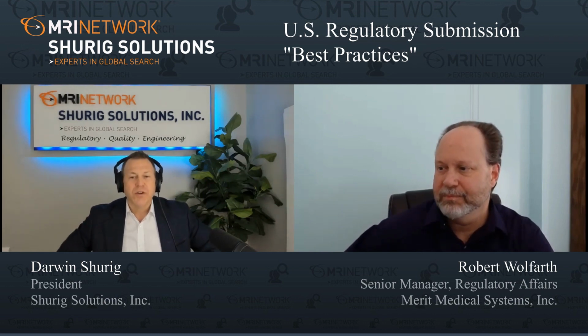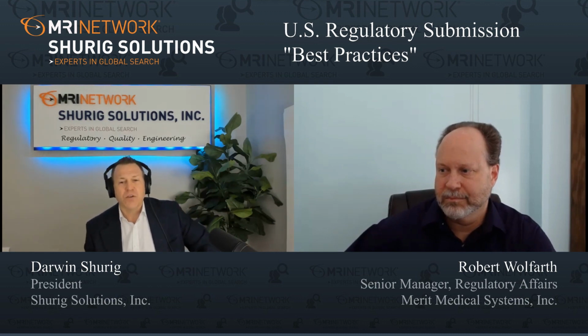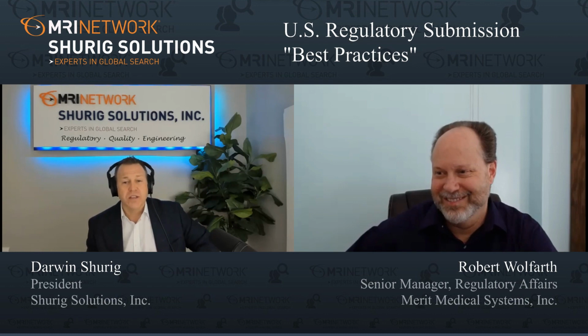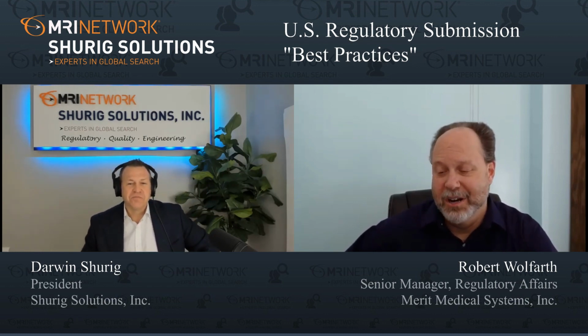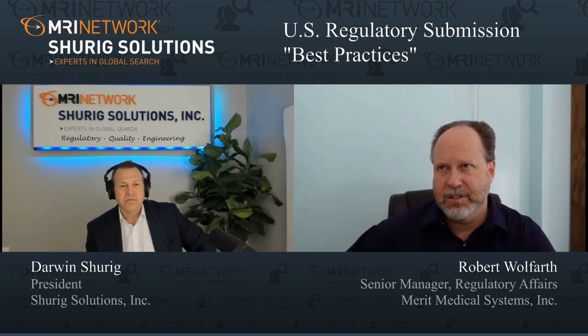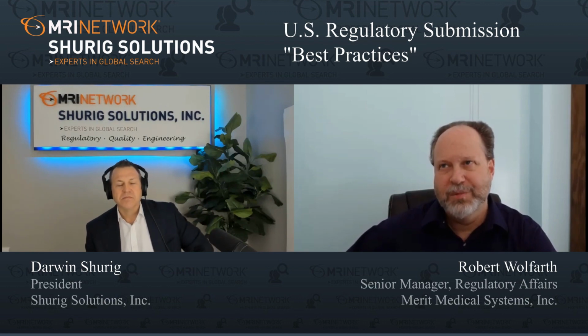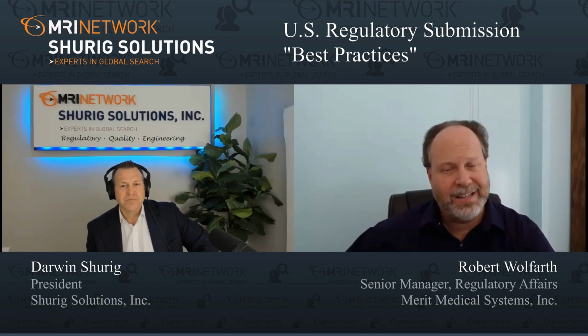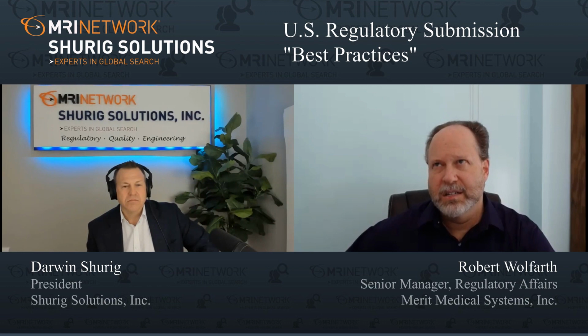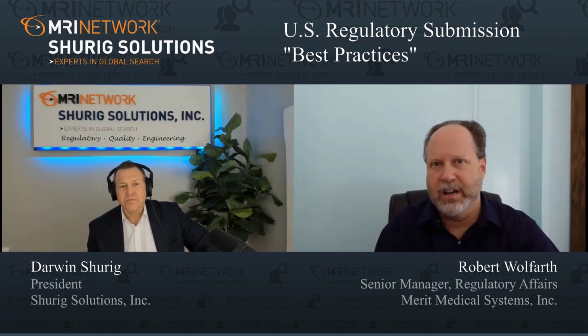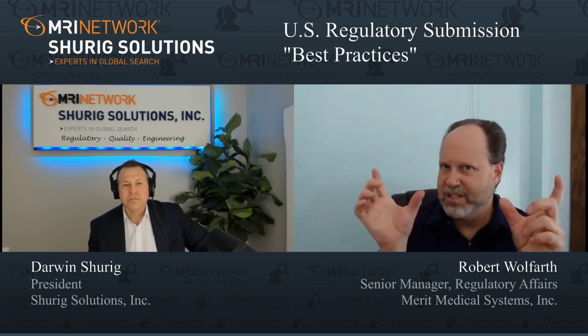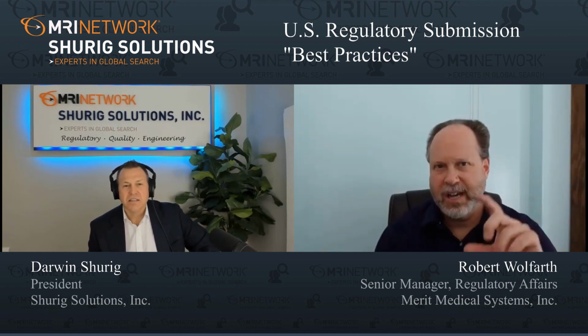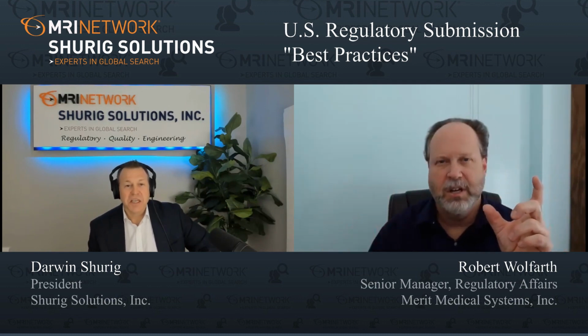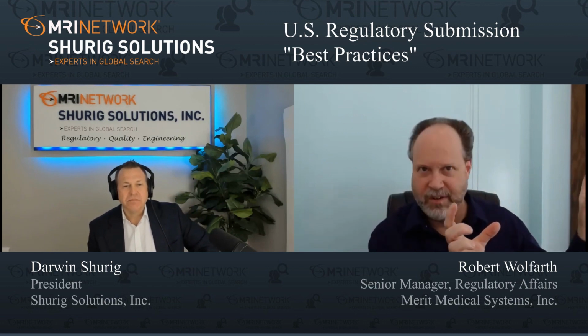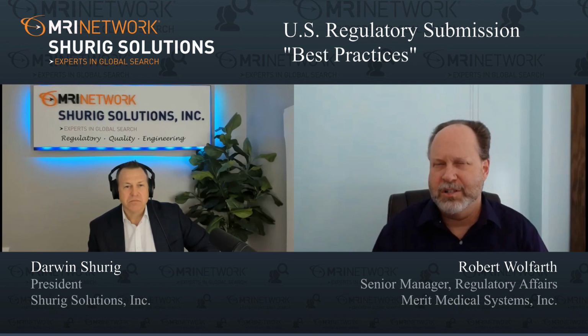So taking two cleared devices, putting them together, a mashup of sorts, each leveraging a substantially equivalent device, but coming together in a new way, but no new real risk. Any general advice? Very good question. FDA has been increasingly reluctant in recent years to clear 510Ks based on multiple predicate devices. In years past, they have done that. But what they're realizing is it doesn't make sense under the substantial equivalence paradigm, where you're saying our device is pretty much the same as their device. Once you start bifurcating that and saying our device is pretty much the same as their device for this purpose, and much the same as this company's device for that purpose, then pretty soon it's no longer substantially equivalent to anything.